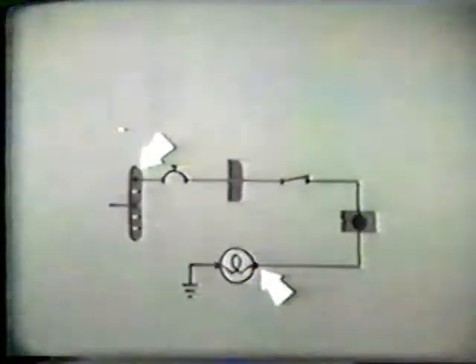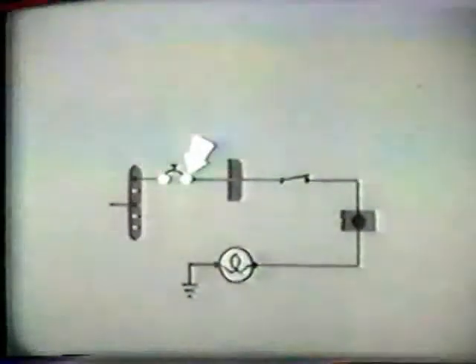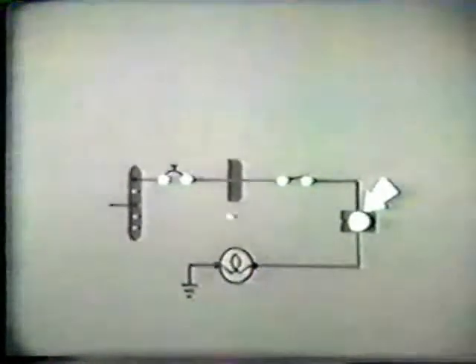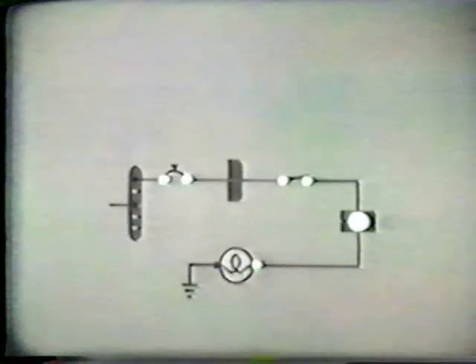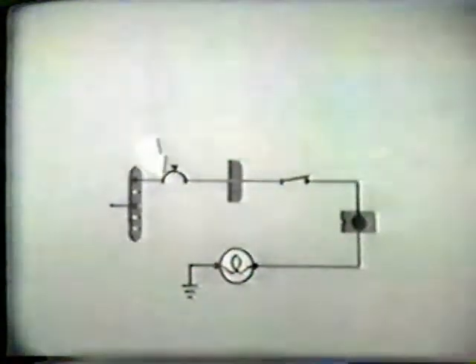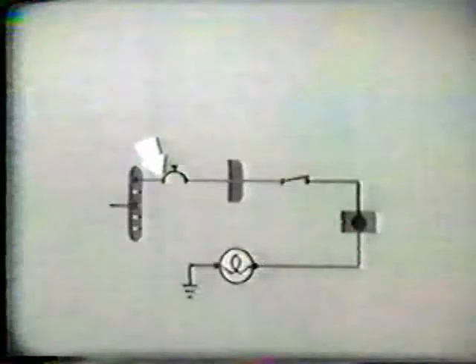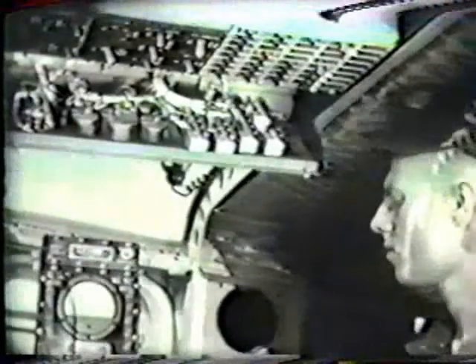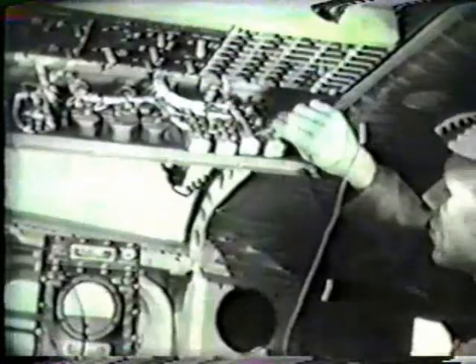The easiest way to find the open is to start at the bus bar and check for voltage at each terminal along the entire circuit. When we don't get a voltage reading, we know we've passed the open. We can start at the primary side of the circuit breaker since this is the first terminal beyond the bus bar. Here's how it's done. The circuit breaker wiring is exposed and the primary side of the navigation light circuit breaker is located. The red test lead is connected to it. The other lead is firmly attached to a good ground. The meter reads 24 volts, so voltage is reaching the circuit breaker.